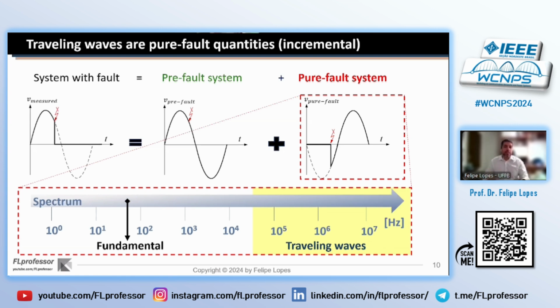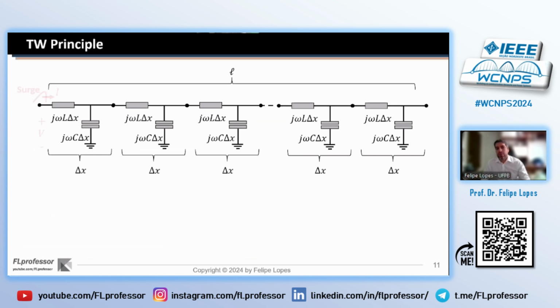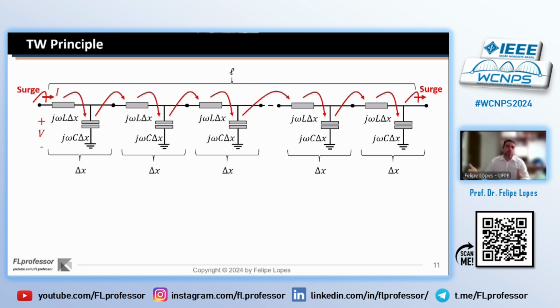And given this step surge, we can understand the propagation of traveling waves just by thinking about the surge that takes place in a given point of the line. It will change the profile of the currents flowing here through the inductance. It will be full of magnetic energy, and then it will pass the remaining energy to the capacitor and so on, in such a way that we can see the surge propagating over the line, having a well-defined travel time. And since these parameters tend to be homogeneous for a given piece of cable, we expect to see a constant propagation velocity for a given type of line.